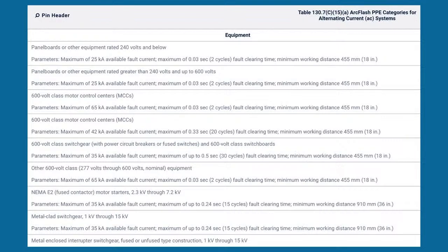Now, I'm just going to make one up here. Let's just say that I'm working on a panel board or some other type of equipment that's greater than 240 volts. We'll just say it is 277. All right. Now, if you look here, there are some parameters right below this. It says a maximum of 25 kA available fault current. If you have 30 kA, you cannot use this table. The hazard risk category method, it's over. Okay. You've got to meet that or lower. Also, the clearing time has to be 2 cycles or 0.03 seconds fault clearing time, and a maximum working distance of 18 inches. If you don't meet any of those, you cannot use this table right here.